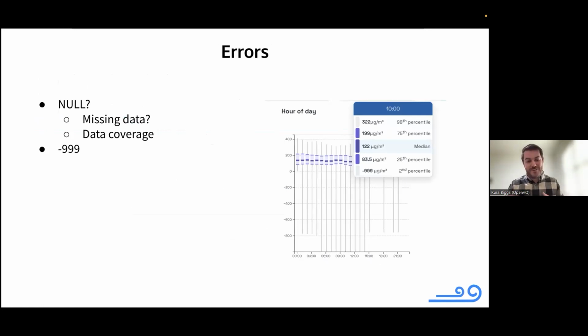Errors: a lot of these machines will just return error data. A big question is, what is null? Is a null actual missing data, or is it an error? This is really important to distinguish, what the instrument is returning. Does null mean the machine was down, or a missed measurement, or an error? This can really affect data coverage. If you're creating averages, it's really important to know if you're missing data.